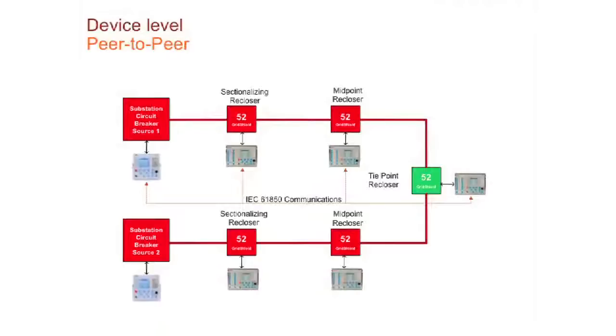So all of these applications work, but they're all based on your requirements and where you want to go in the future. The whole point for a centralized one obviously requires communication. It's a higher investment, but it takes into consideration the whole network. So not only do you do the reconfiguration, but later on you could also perform algorithms to optimize your volt-VAR, your power factor, and so on, after you've actually isolated and reconfigured the system.